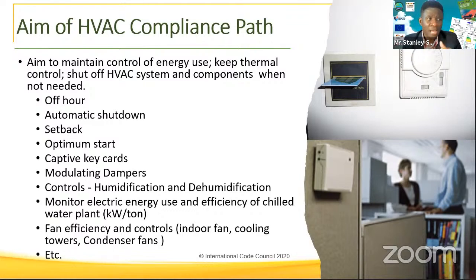Off, setback, optimum start. Optimum start is not as popular in the region, but we tend to have an optimum start program where we ensure that the temperature conditions are achieved at the required times. So if persons come to work at 8:30, you probably can have the AC turn on from 7, with a set point of maybe 27 degrees C, and then gradually go to 24 degrees C.